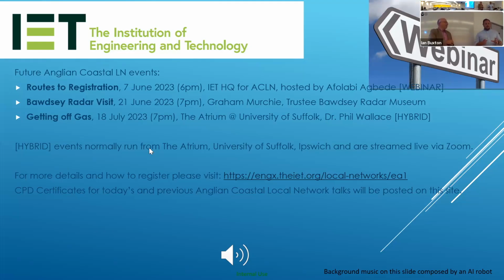For the onshore route, for the EA1 project you're talking about, we have a trefoil cable, so a 3 core cable - there's 2 of them offshore, so 6 cores in total. When they come offshore, they're bundled into 1 cable, so you've got a 3 core cable, you pull them into one HDD, and then they split out onshore so that the thermal performance is increased. You split the cables onshore into individual cores because it's easier to dissipate the heat that way for the East Anglia 1 cables. Is that DC? No, that's AC. For East Anglia 3, which is DC, they would have installed the same HDDs, but we've just got 2 conduits, one for each pole, and then a fibre optic one on top. So yeah, it's really just for the thermal performance.